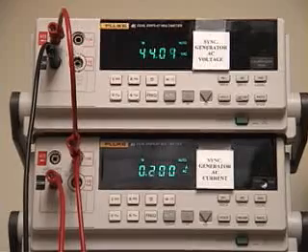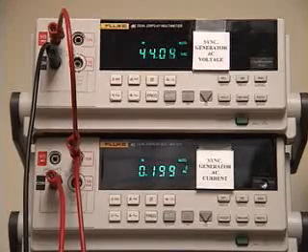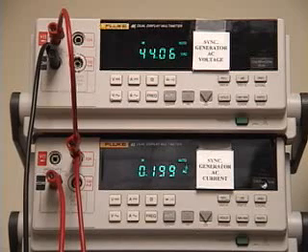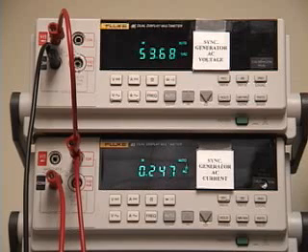A voltmeter and ammeter pair is connected to measure a per-phase output of the synchronous generator. In this case, A phase to neutral in the voltage and A phase line current. In the synchronous generator, the magnitude of the AC voltage is controlled by the DC excitation current. Notice how varying the DC excitation current and increasing it increases the voltage output on the top meter. I'm going to adjust it to a nominal 120 volt output.